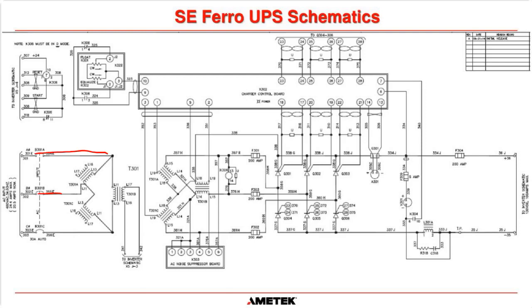So we have our three-phase coming in here. Once again, A phase, B phase, C phase. And you notice there is no neutral being run here because this is a delta transformer, and a delta transformer does not need a neutral. Okay, so don't run a neutral to the UPS because there's nowhere to actually tie it to. You want 3-wire and ground to our UPS systems because all of our inputs are a delta transformer.